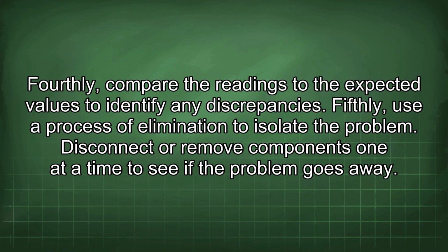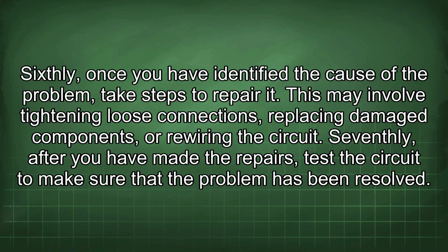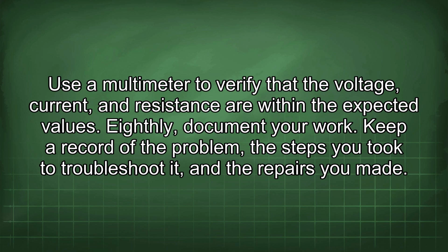Fifthly, use a process of elimination to isolate the problem. Disconnect or remove components one at a time to see if the problem goes away. Sixthly, once you have identified the cause of the problem, take steps to repair it. This may involve tightening loose connections, replacing damaged components, or rewiring the circuit. Seventhly, after you have made the repairs, test the circuit to make sure that the problem has been resolved. Use a multimeter to verify that the voltage, current, and resistance are within the expected values.